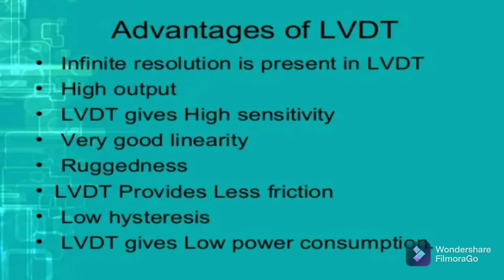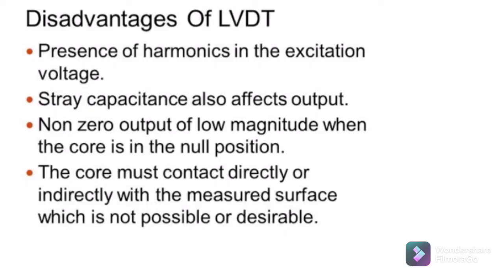Now we will move on to the disadvantages of LVDT. The first disadvantage is that since LVDT is an inductive transducer, it is sensitive to stray magnetic fields, hence extra setup is required to protect it from stray magnetic fields. The second disadvantage is that since it is an electromagnetic device, it also gets affected by vibration and temperature variation.